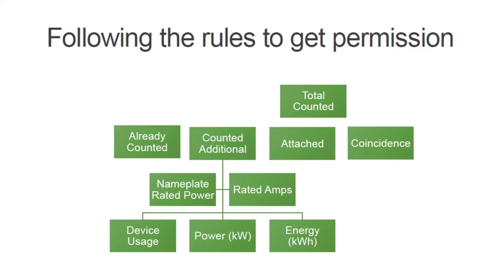What gets counted additional to those loads are things that are attached. One interesting attached example is, let's say you have a 1200 watt microwave. If it's a countertop microwave, it doesn't count as an additional load. But if you screw it to the wall, it is now an attached load to your house, and the code now counts 1200 more watts of attached load. And then it would be multiplied by its own coincidence factor. Let's say it was beyond the 8,000 watts, so it was a 40% coincidence factor, so it's 40% of 1,200 watts, so a little more than 400 watts.